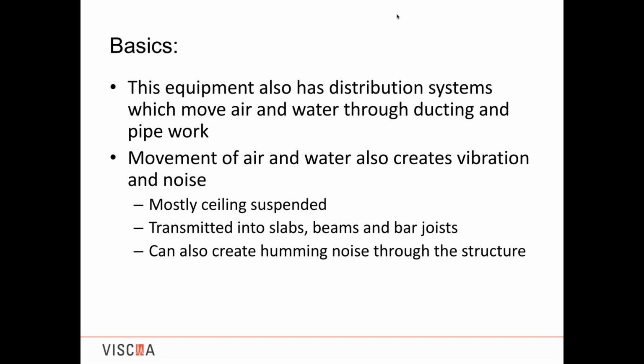Now, aside from the equipment itself creating some vibrations, the distribution systems for this equipment, since we're working in HVAC, we know we're moving air and water through ducting and pipe work. That movement of the air and water through the distribution system will create its own problems. When the pipe or the ductwork is going through a floor penetration, it creates vibration into the building structure. And when the equipment is rigidly attached to the piping and ductwork, the vibration from the equipment itself will be transferred through the ductwork and the pipe and then into the building that way.